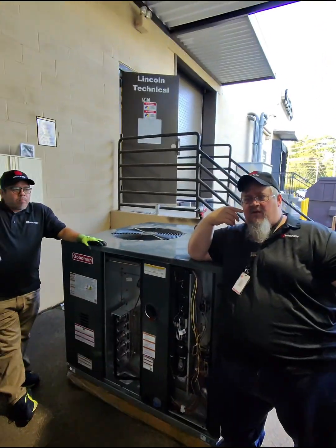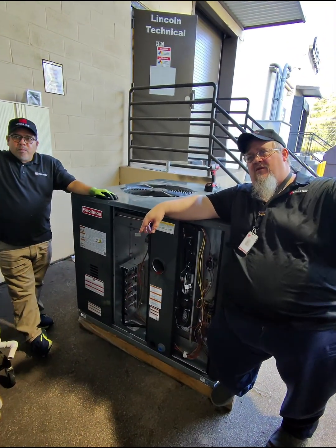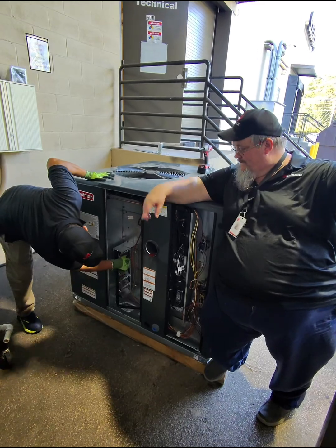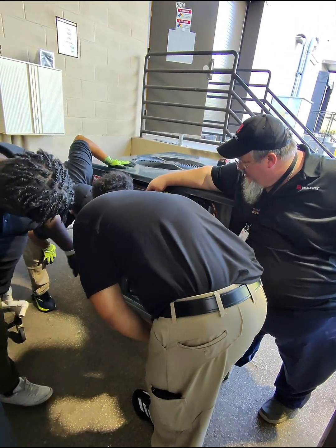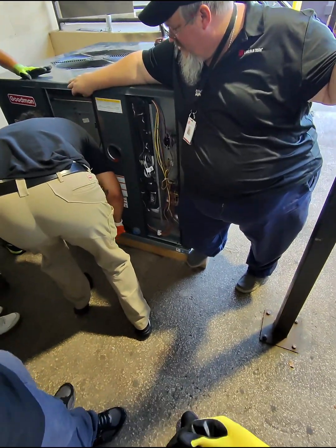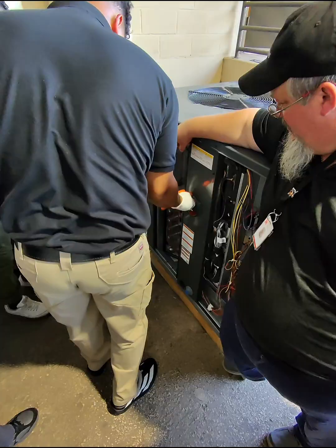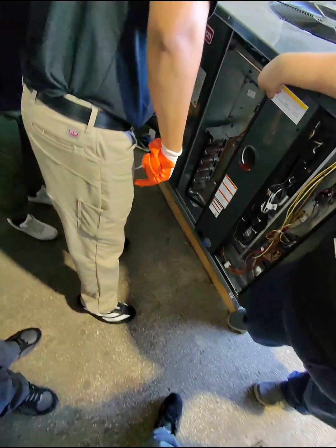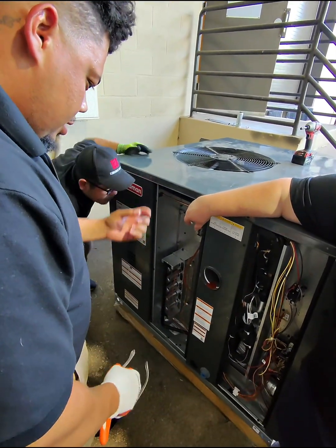Yes, sir. All right. Speaking of safeties, where are the safeties that we have on this? We have several safeties on this. I see the rollout switch right here. Okay, that's the rollout. Where's our other one? Take this off? You can. You may have to take these two screws out up top if you do. That one and this one. This panel's kind of a bugbear to get on and off, but you got to see the high limit switches. What's the high limit switch?